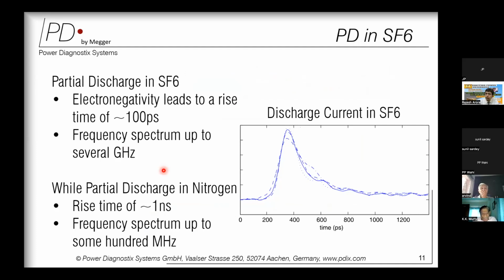Partial discharge phenomenon results due to the discharge current in any insulating medium. And this discharge current could provide a different signature in different insulating media. So whenever we talk about partial discharge in SF6 gas, why do we say the UHF method is useful? It generates a discharging current pulse which could have a typical rise time of 100 picoseconds, and if we convert that into a frequency spectrum, it could range up to several gigahertz. And the frequency spectrum from the higher frequency range of hundreds of megahertz to gigahertz is called the ultra high frequency band. And that's why we call the sensor technology used UHF sensor technology.